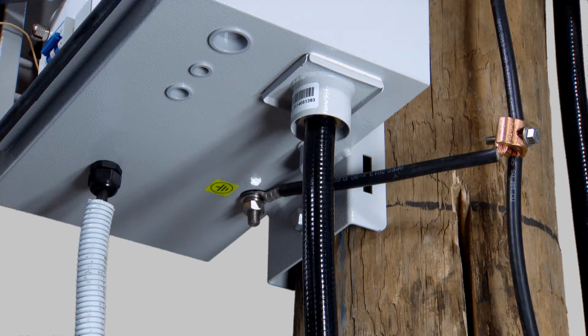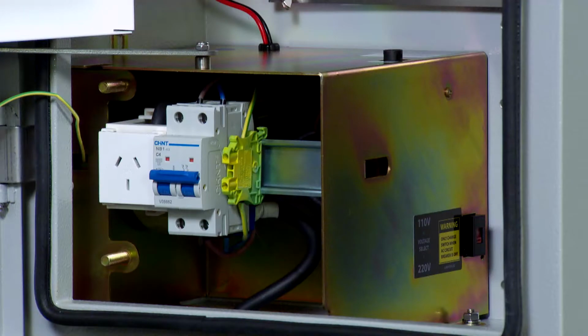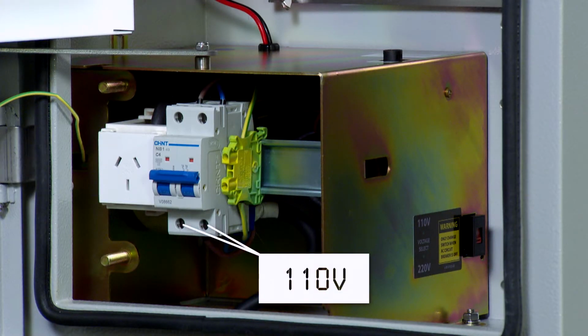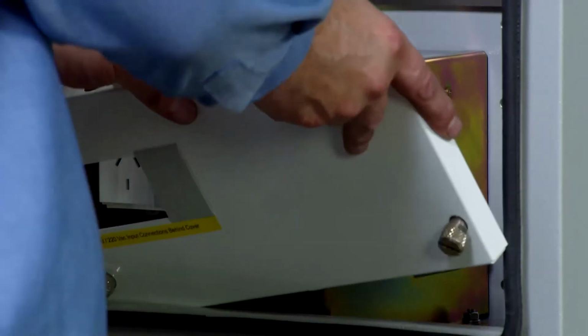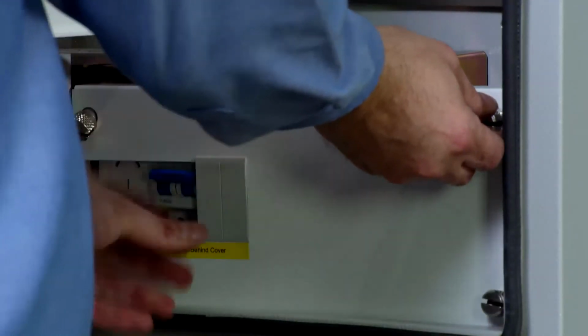All cables taken into the RC10 must be sealed and secured with glands to maintain the IP rating of the cubicle. If low-voltage supply is available, measure the incoming voltage to confirm the VT is supplying the correct voltage to the RC10. Refit the lower escutcheon plate when cabling is completed.